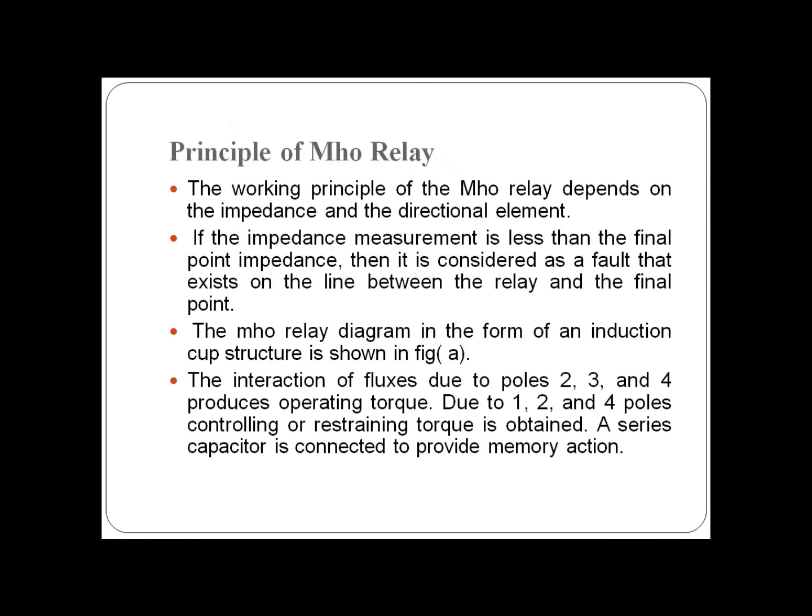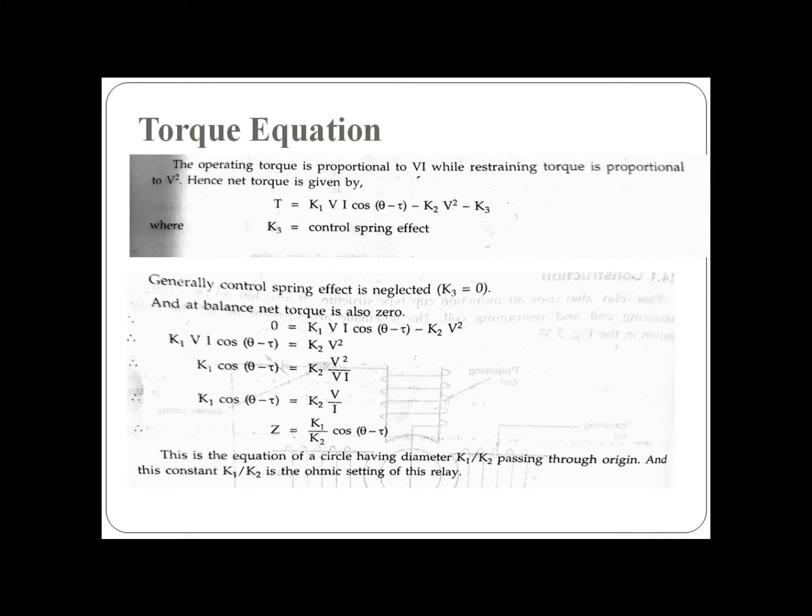These are torque equations of a Mho relay. The operating torque is proportional to VI, while restraining torque is proportional to V². The total torque T equals K₁VI cos(θ - τ) minus K₂V².